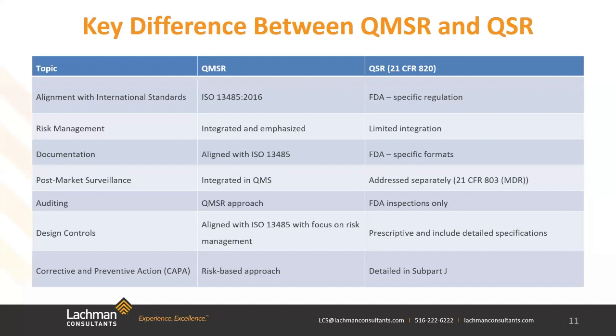That is why FDA will not accept ISO 13485 certificates. FDA does intend to replace the current QSIT inspection approach with one that will be consistent with the requirements of the QMSR. Currently, FDA is evaluating the MDSAP audit approach and plans to develop an inspection process and train their inspectors to that. So they're still working a lot of this through. I know that there are 14 months before the QMSR is fully implemented.